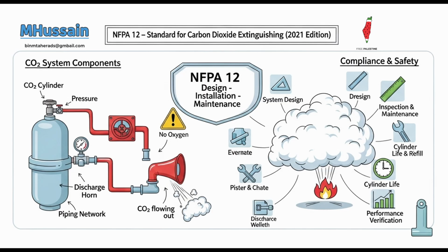Okay, so beyond those exceptions and retrofits, what are the general safeguards needed for any CO2 system to protect people? To mitigate these inherent dangers, the standard outlines comprehensive safeguards that must be in place for any CO2 system, not just total flooding. For evacuation procedures, this means ensuring adequate aisleways and keeping exit routes clear at all times. Clear paths out. It also mandates necessary additional or emergency lighting and clear directional signs to ensure quick and safe evacuation in low visibility conditions. Lighting and signs, crucial in that white cloud. Absolutely. Exit doors from hazardous areas must be outward swinging, self-closing, and equipped with panic hardware, if latched, to allow rapid, unhindered escape. Panic bars, push outwards, standard stuff, but vital here.